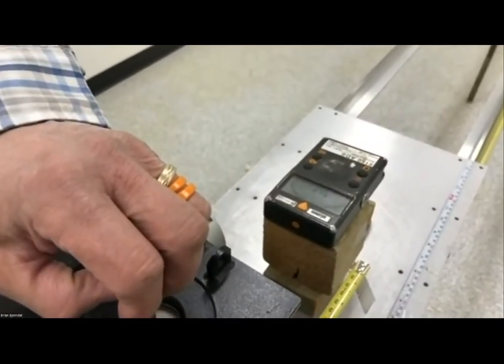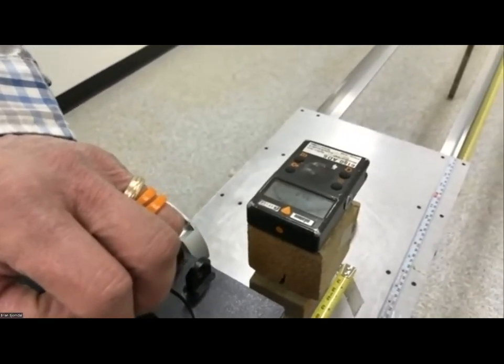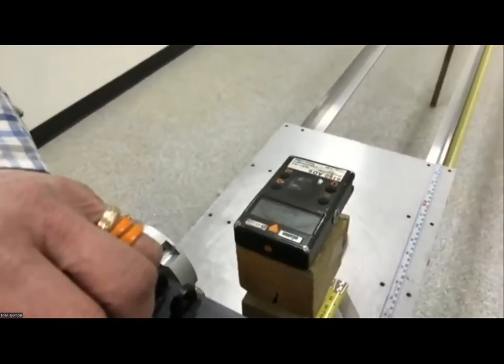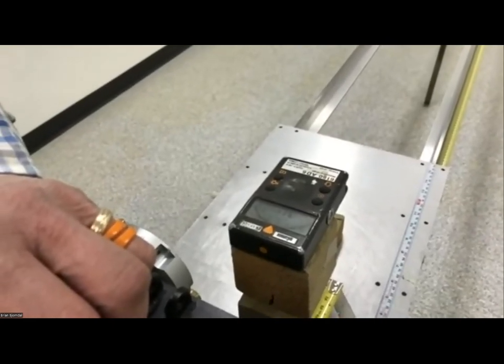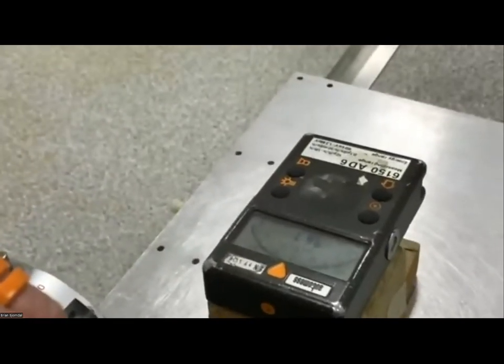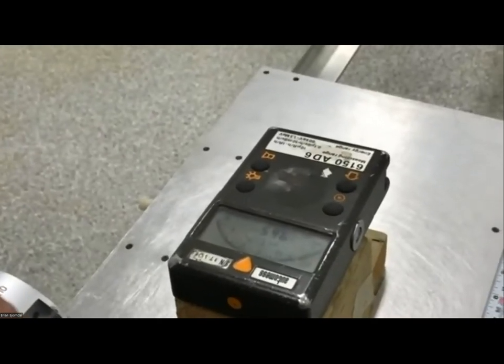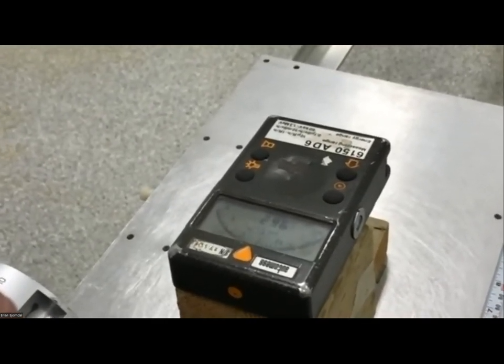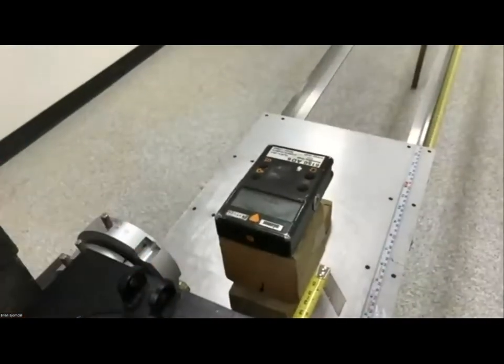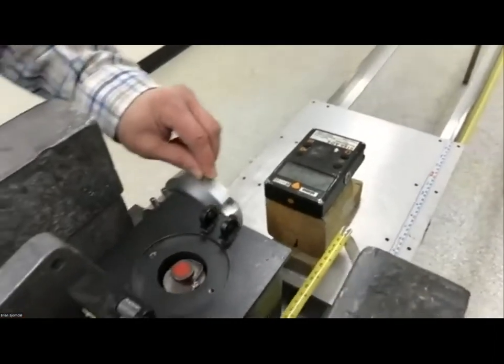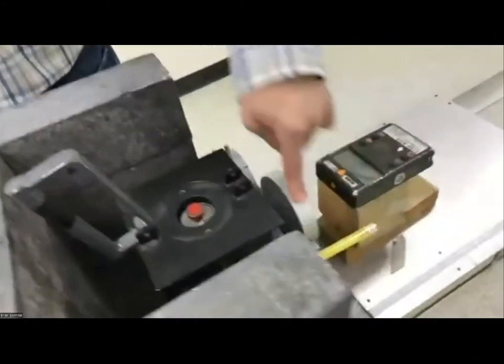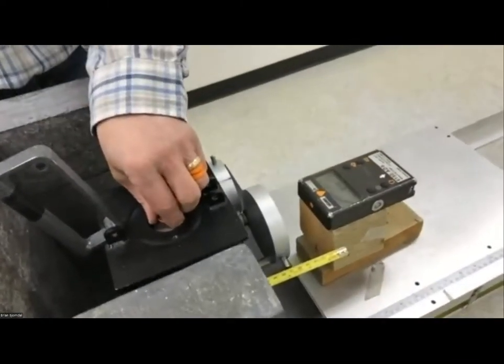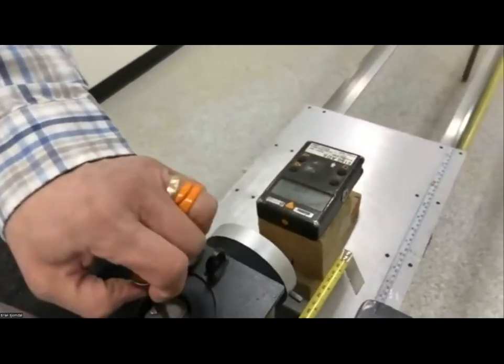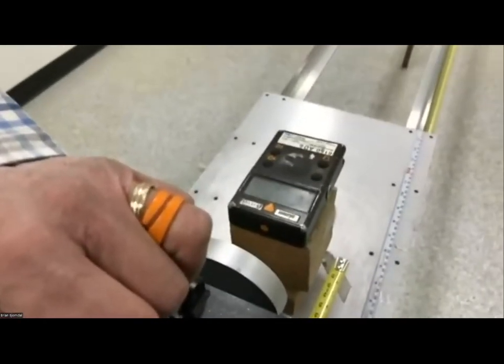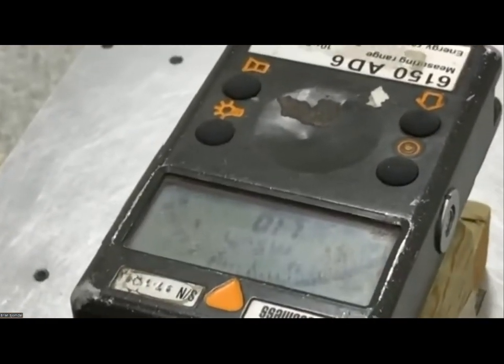And you can see this AutoMess is performing quite nicely. It's about 9.75. When you're doing exposures, the instrument will fluctuate a little bit. So you sit there and wait till the reading stabilizes, and then the technician will take a reading. When he or she is done taking that reading at that desired dose rate, they'll drop the plunger. And what we can do is introduce an attenuator. If I throw a times 10 attenuator in here, I'm going to drop that dose rate by a factor of 10. If I open up the plunger again, you're going to see now I'm at an expected dose of around 1 millisievert per hour.